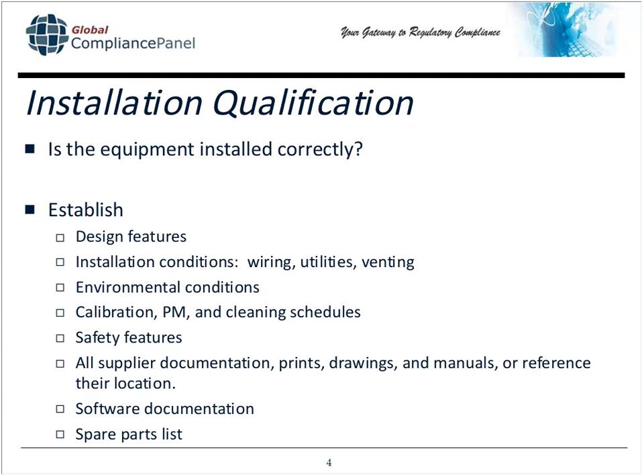Most of the time when you purchase a piece of equipment that you're going to use in your assembly process, in your manufacturing process, it comes with an operator's manual, which does contain calibration processes and frequencies, preventive maintenance, and cleaning schedules, how often you have to clean maybe a platen or something like that. What type of safety features you use need to be established also. Are there any open areas? What about a user safety perspective? If there's a long cord, but you have this unit close to the wall, is there going to be 6 or 8 feet of cord that may drag on the ground and may present user safety implications?